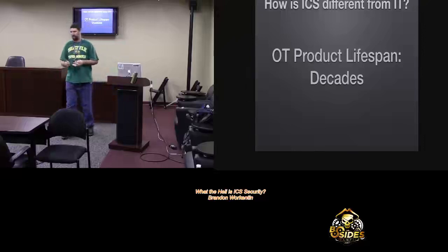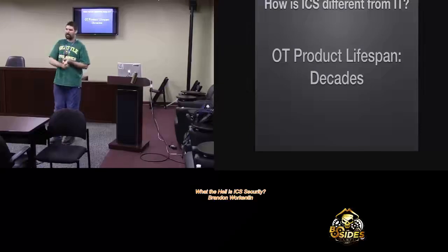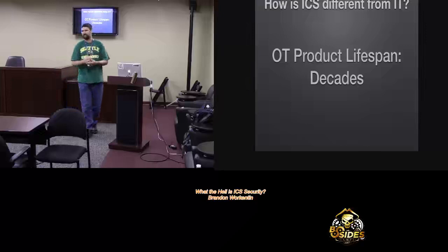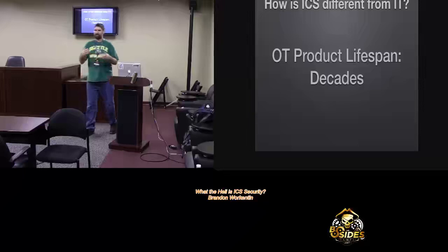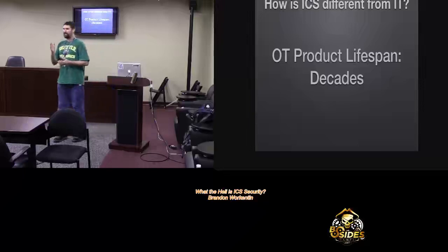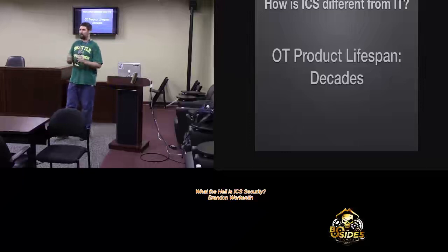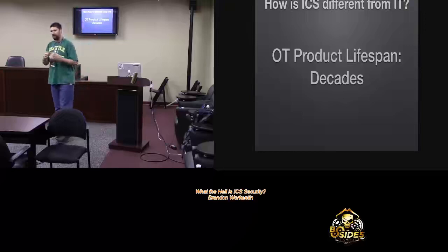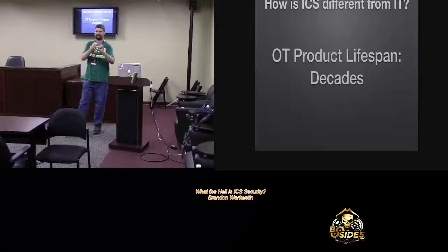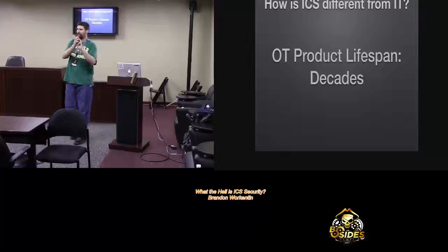The reason they're that old is because they cost $1 million or more per item. One reason they cost so much is the lead time to make them is so long, a year or more. One reason the lead time is so long is that the average large power transformer design was made 1.3 times. So everything is made to spec — 1.3 times means that for every 3 designs, 2 are made to spec, and the third one is made twice.